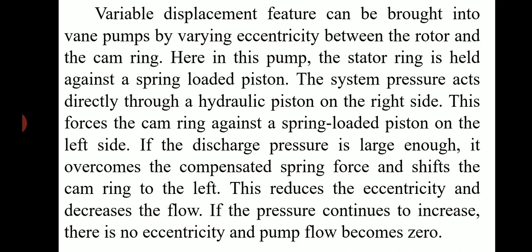If the discharge pressure is large enough, it overcomes the compensator spring force and shifts the cam ring to the left. This reduces the eccentricity and decreases the flow. If the pressure continues to increase, there is no eccentricity and pump flow becomes zero.